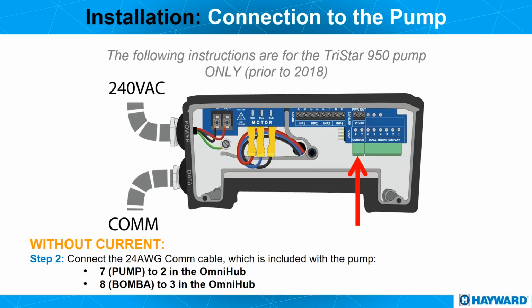In the case of a TriStar 950, which was an older model, we have this little plug called the communication bus. All we have to do is 2 wires instead of 3, and that will connect to our automation system and control the pump.